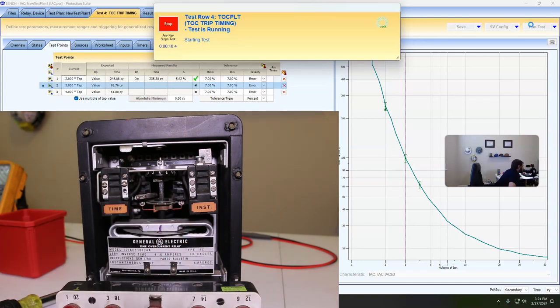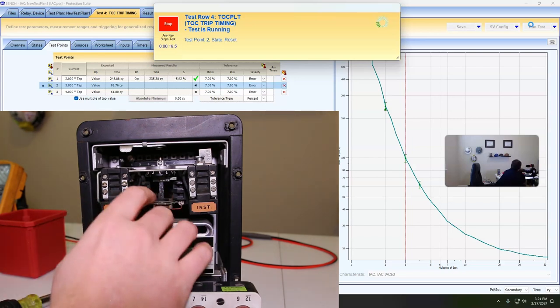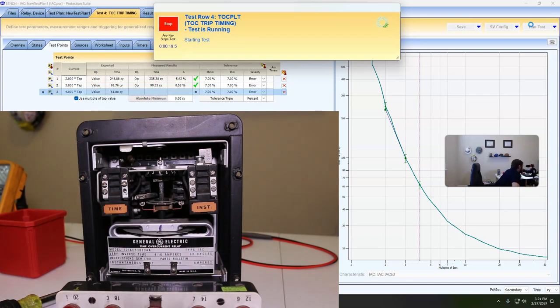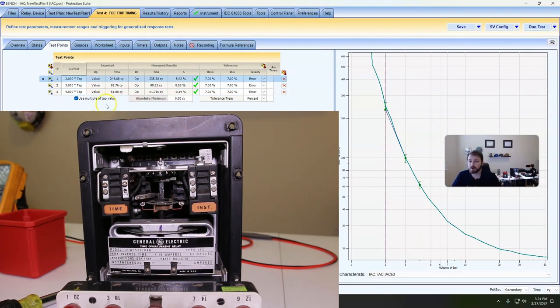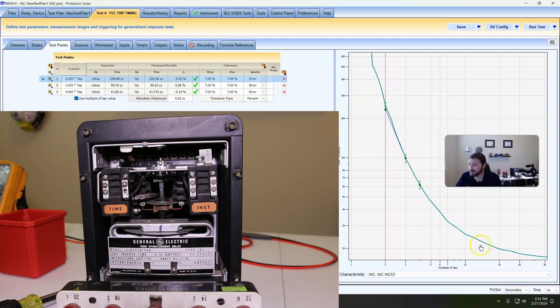Just manually pushing the disc all the way back to reset position. And look at that — perfect timing. Obviously not perfect — this is a 50-plus year old unit — but we match our expected curve very, very well. That's exactly what we want to see.